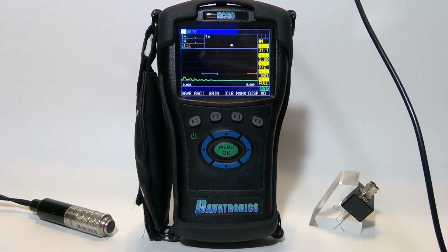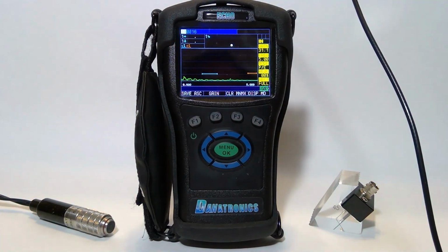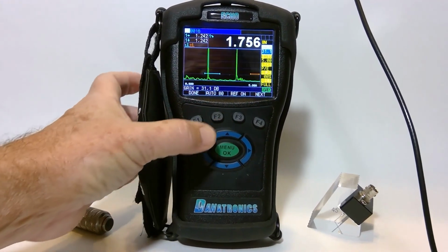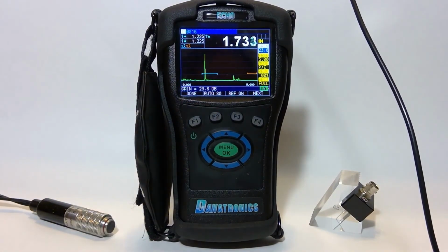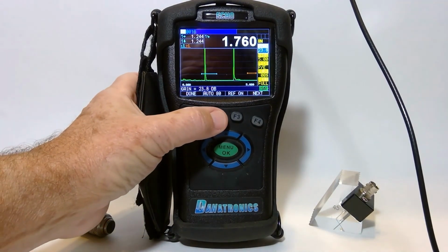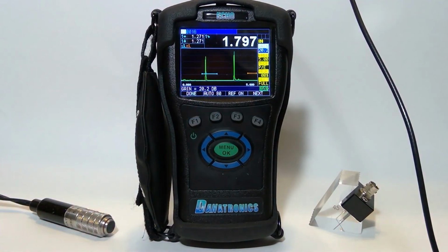I'm going to use display mode number 2. It has a little bit larger readout at the top. I couple on my block. And on this particular setup, I'm going to be using a Type 2, as I mentioned, with my echoes coming up at 2 inches and 4 inches. I have too much gain. I can use Auto 80 under F2, and it'll automatically put those echoes at 80% full screen height. Try and peak up on both of them. There we go. So that's what the screen will look like.